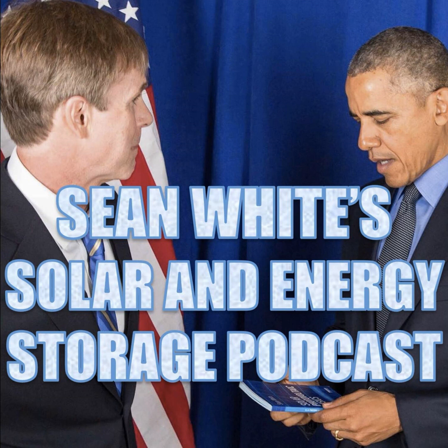Some people say they're too sensitive because if you replace an old grounded inverter with a newer ungrounded inverter, we're using the old terms here now, and that's okay. But a lot of times when people are replacing these older inverters with these newer inverters, they can't get them to turn on because it's showing ground fault, ground fault, ground fault. One of the easier ways to deal with that problem might be programming the inverter to be a little bit less sensitive. Or be a genius and go find out what's causing all those ground faults. You might have to rewire your system though.